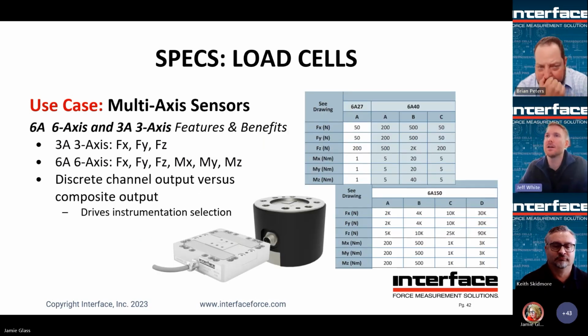So more multi-axis, these get a little bit more complex. We speak a lot about how our low profile load cells have the ability to ignore off-axis and side loads, but what if those forces are important to you? We offer a full line of 3A and 6A load cells. Depending on which load cell you choose, it will also drive the instrument that you need. The 3A offers your FX, FY, FZ. It is very symmetrical and has discrete channel output, whereas the 6A will deliver a composite signal. You can see all your axial forces as well as all of your moments. And this needs a matrix to decipher what direction and force value the force is coming from.